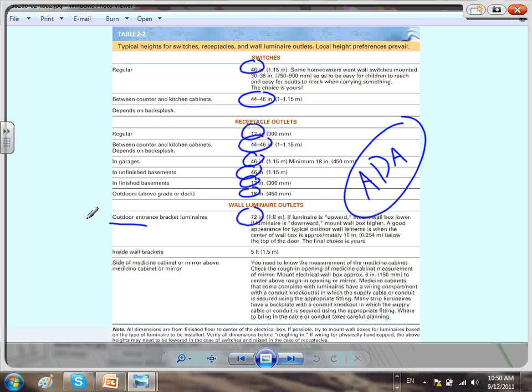What I always tell people is you use these as a keynote or general note, where you say all receptacles shall be installed 12 inches above finished floor, on center. That's a good general note. There are two types of notes: specific notes and general notes. A general note would state all receptacles shall be installed 12 inches above finished floor.